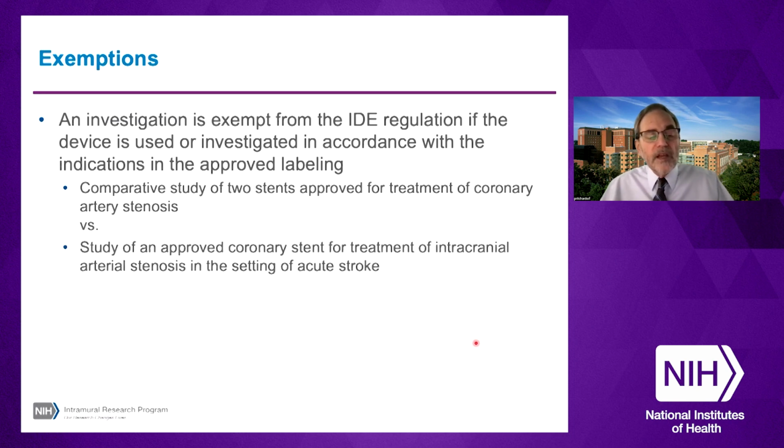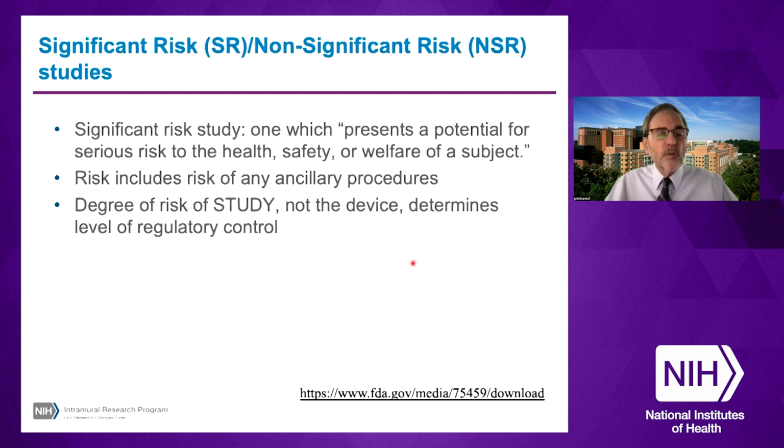In contrast, if an interventional neuroradiologist wants to use one of these same stents to study its use in the treatment of intracranial arterial stenosis or blockage in the setting of acute stroke, then the IDE regulations would apply, because you're using a device which is legally marketed, but you're not using it in accordance with its labeling, and you're conducting a study of the safety and effectiveness. So here in the second example, the IDE regulations would apply, and we'd go on to the next question, which is significant risk versus non-significant risk studies.